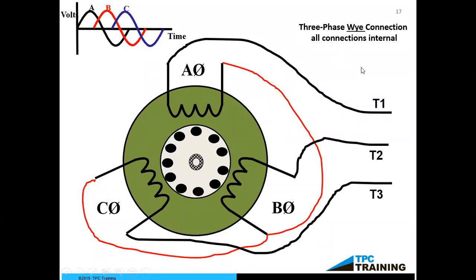So I mentioned earlier that we need that multimeter to identify if our windings are good or not. Basically, what I would do with just a regular ohm meter is put one lead on T1 and one lead on T2, and that is going to force the current straight through winding A, also straight through winding B, and then it would come back out to my ohm meter.